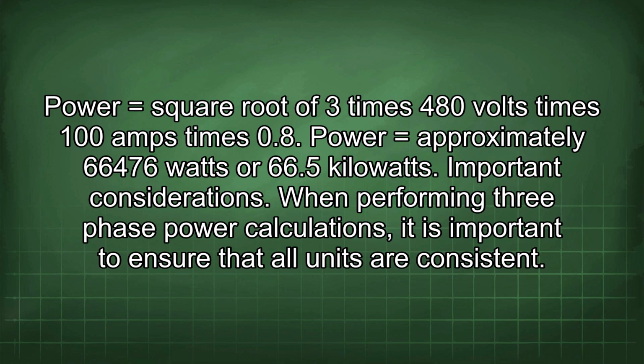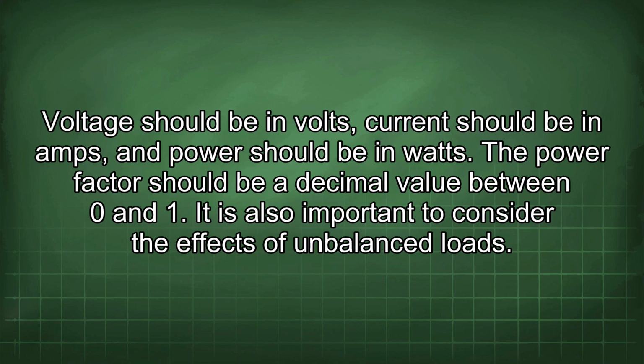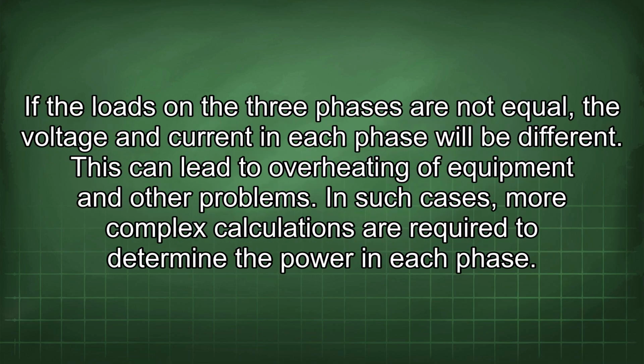Important considerations. When performing three-phase power calculations, it is important to ensure that all units are consistent. Voltage should be in volts, current should be in amps, and power should be in watts. The power factor should be a decimal value between 0 and 1. It is also important to consider the effects of unbalanced loads. If the loads on the three phases are not equal, the voltage and current in each phase will be different. This can lead to overheating of equipment and other problems. In such cases, more complex calculations are required to determine the power in each phase.